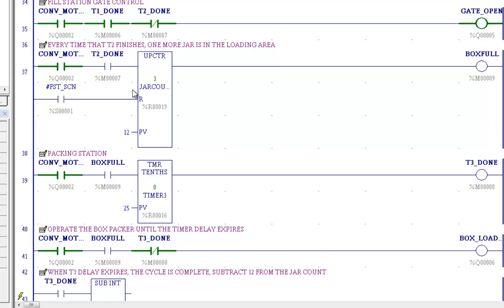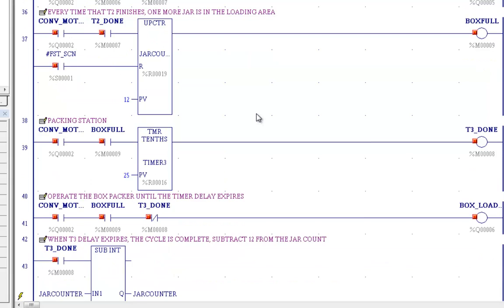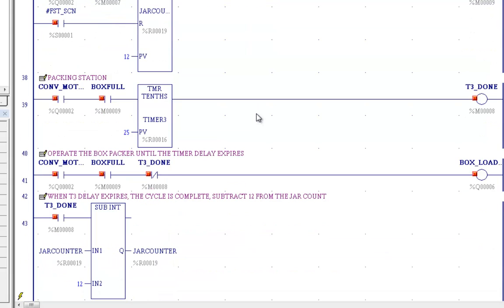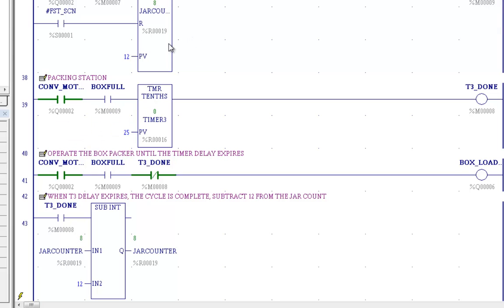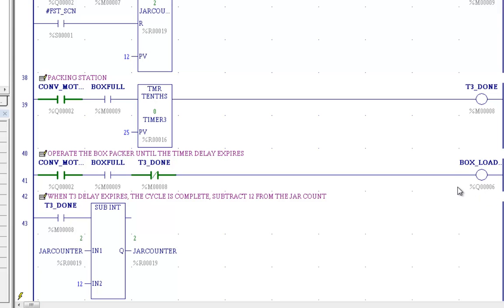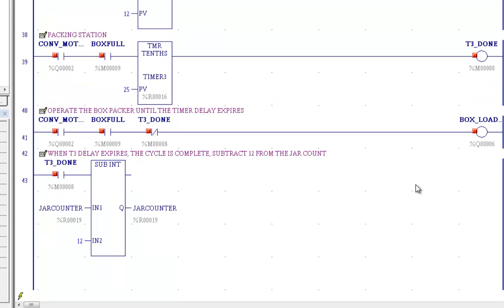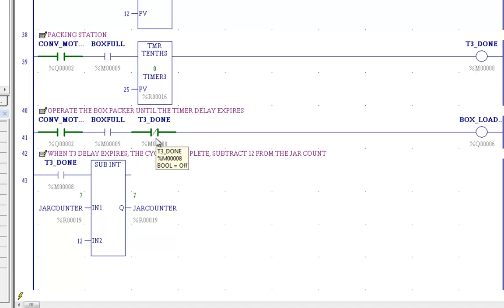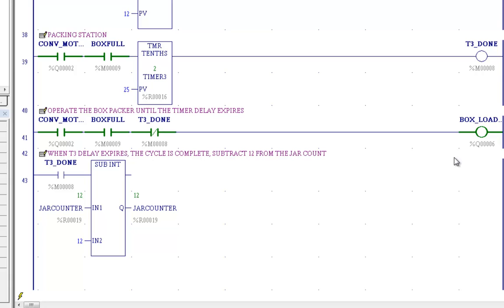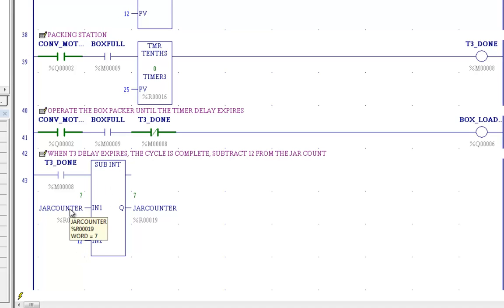Now you look at the box filling station. Every time the conveyor motor is running and the box full area, meaning we've got 12 jars in the staging area, we're going to start our two and a half second box packing cycle. So it's full, two and a half seconds. Conveyor motor is running. When the box is full, and whenever that timer is not done, that will be our box loading. So now you can see the box is loading. As soon as the timer completes, it will reset. It will come down here. As soon as this timer completes, it enables some subtraction. We subtract 12 from the jar counter, and we continue on at that point. Once we subtract 12, we'll no longer have a box full, and the process continues.